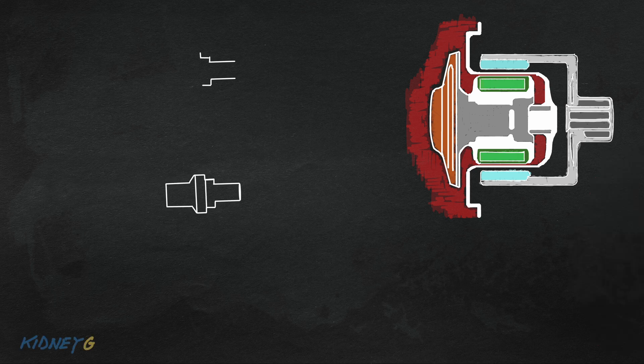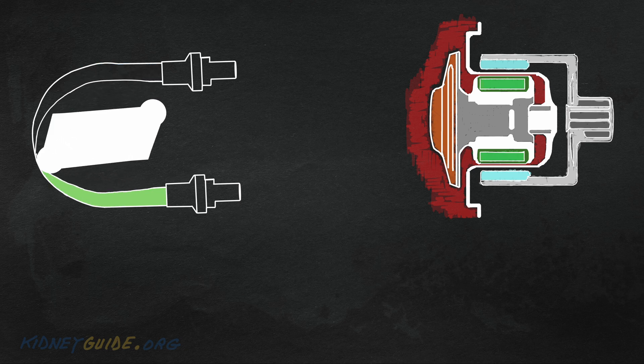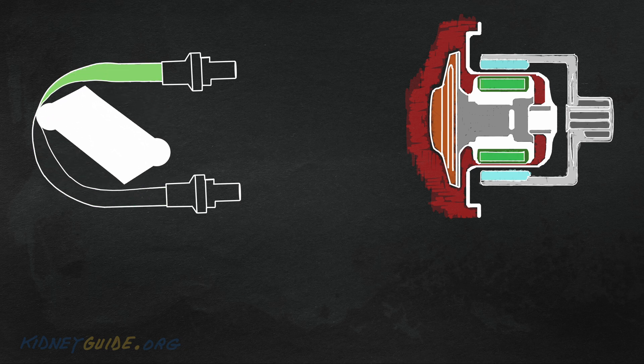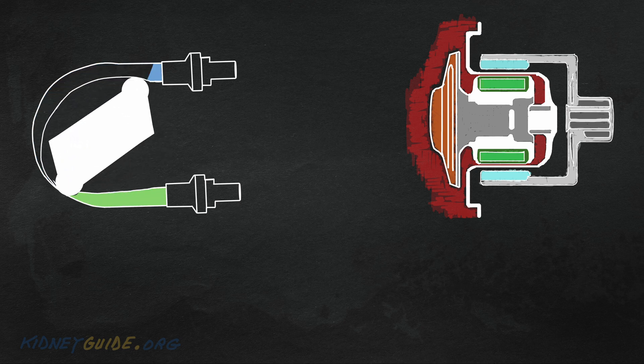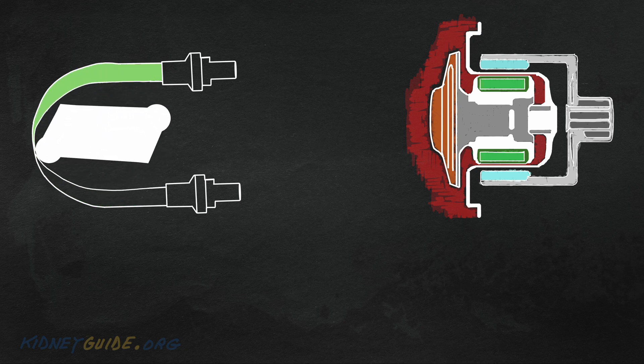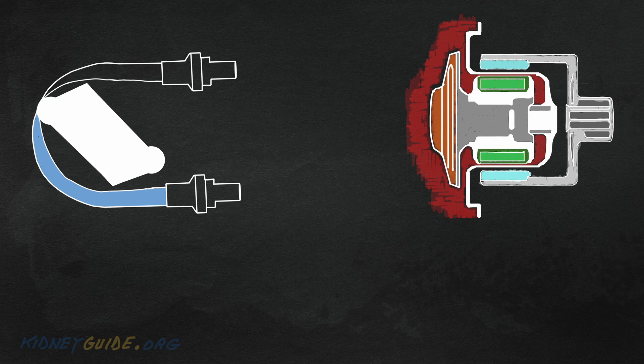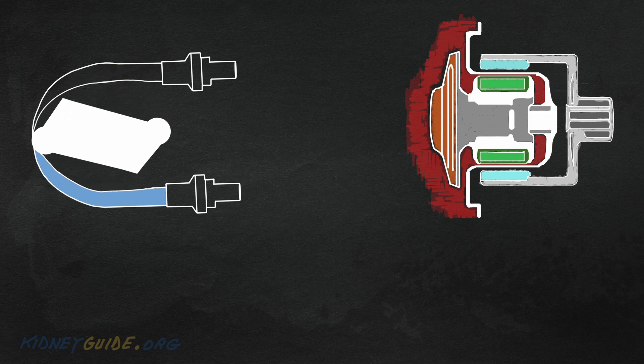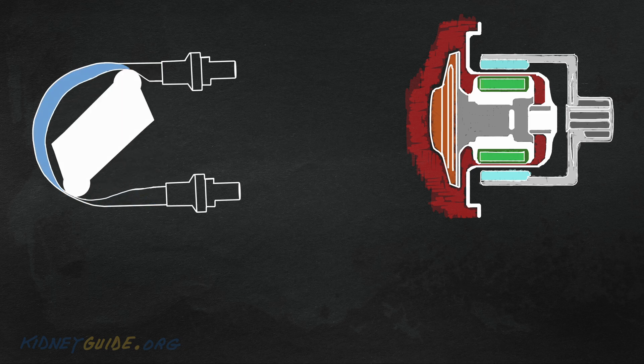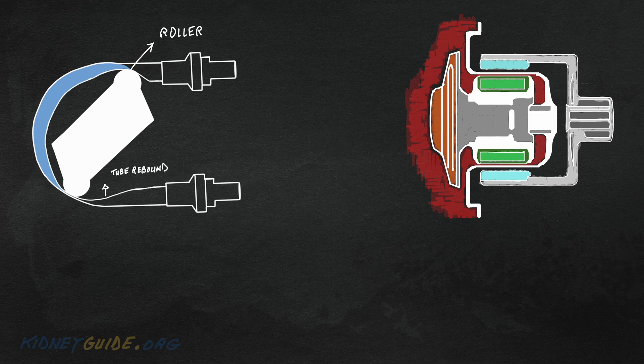In comparison, roller pumps are a type of positive displacement peristaltic pumps. The rotor has a number of rollers, two in this case, which presses the tube as they rotate by. The part of the tube which is compressed is closed, forcing a constant amount of blood to move through the tube. Importantly, as the tube bounces open after the roller passes, blood is drawn into the tube from access. That's how you get your negative pressure.